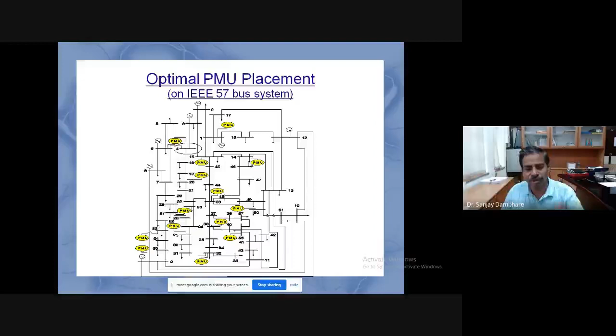You can refer to this, and the paper is published in IEEE Transactions, that PMUs are to be deployed on one third of the buses. So if the system is of 100 buses, then almost 30 buses are required to be deployed with PMUs to make the system completely controllable and completely observable. Yeah, this is the first initiative of WAMS worldwide. It was in North America, and they used these PMUs for monitoring, improving state estimation, post-fault analysis, operator information, oscillation damping, etc.